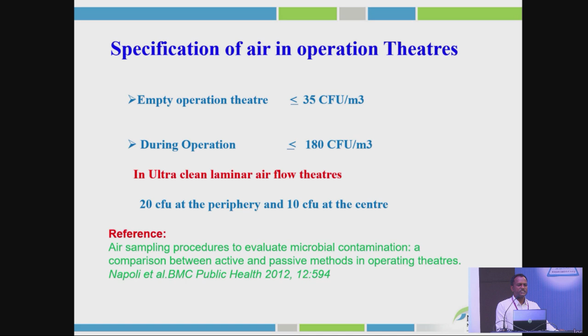Once you've done the air sampling or settle plate, there is some criteria for the microbial load. In an empty theatre, the colony count should be less than or equal to 35 CFU per meter cube, and during operation should be less than or equal to 180 CFU per meter cube. In ultra clean laminar filter theatres, it should be 20 CFU at the periphery and 10 CFU at the center.